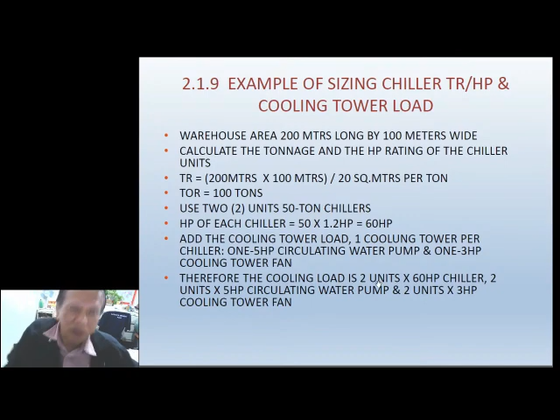Okay? So, warehouse na ito, 200 times 100 divide by 20 square meters, 100 tonner yung chillers mo. So, if I have 2 units of 50 chillers, then I will have 50 times 1.2 is 60 horsepower. Then, each chiller will have a drive of 60 horsepower. And then, pag may chiller ka, meron siyang kasabay na isang circulating pump, usually mga 5 horsepower, at saka isang cooling tower, usually ang fan na yon 3 horsepower. So, 60 horsepower motor for the chiller, 5 horsepower motor for the circulating water pump in the cooling tower, and a 3 horsepower motor that drives the fan of the cooling tower. So, anong load mo? 60 horsepower, 5 horsepower, 3 horsepower. And since there are 2 chillers, dalawa yan. 2 sets yan. Okay? So, ventilation naman.